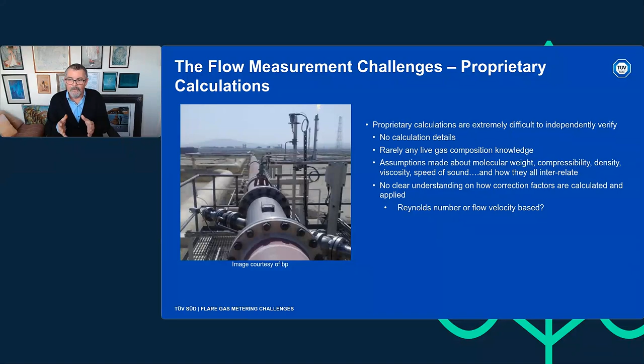Because it's proprietary, there's no clear understanding of how any correction factors are calculated and applied. If you're applying corrections based on flow velocity, how accurate is that velocity? If there's a bias from an installation effect, your flow velocity may not be representative. If you're using a Reynolds number based correction factor, which seems the common sense approach, how accurate is your Reynolds number? If it's based on assumptions about gas composition that are untrue, your viscosity might not be accurate, your density might not be accurate, your velocity might not be accurate because of installation effects. The Reynolds number equation, rho V d over mu, how accurate is it? If you don't know, there's a great danger you're applying the wrong correction factor for any given flow velocity.